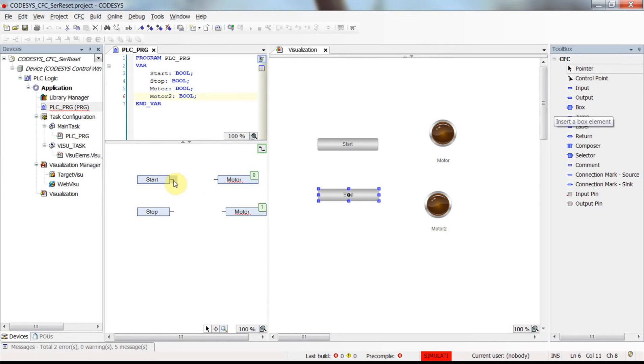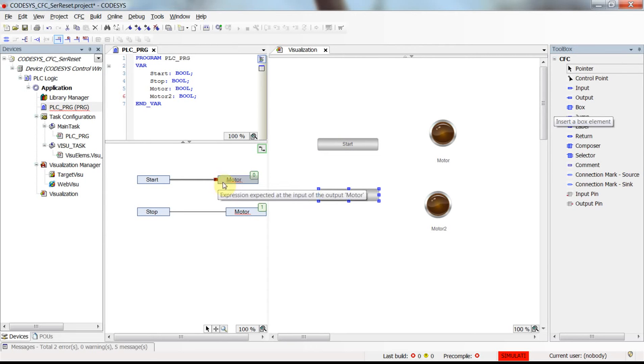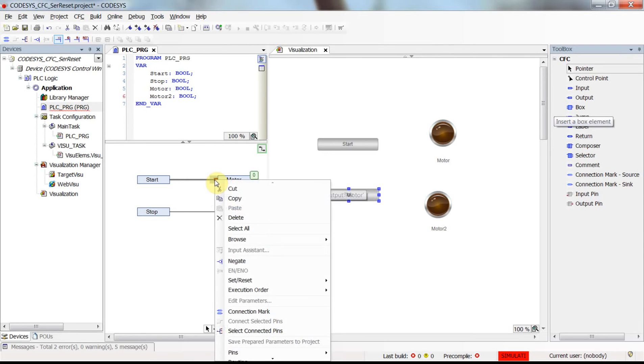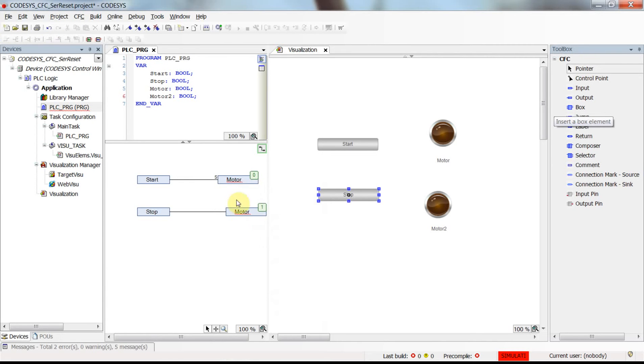Now I make a connection from start to motor by clicking on the pins, and the same for the stop connection. I want to set the motor whenever start becomes true, so I need to change this coil into a Set coil. I do this by right-clicking on the input pin of the output element and choosing Set. You can see the 'S' character now appears at the input of the motor output element.